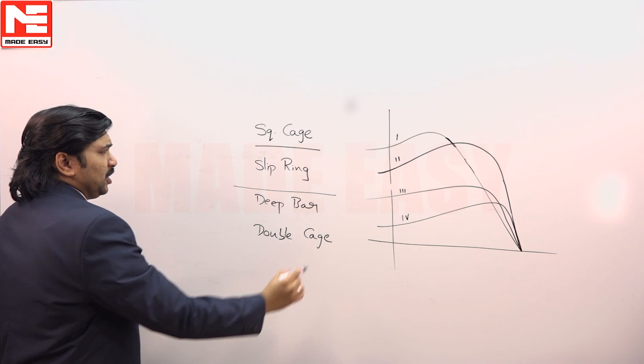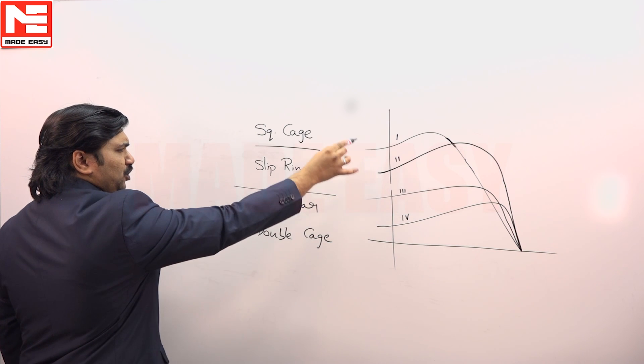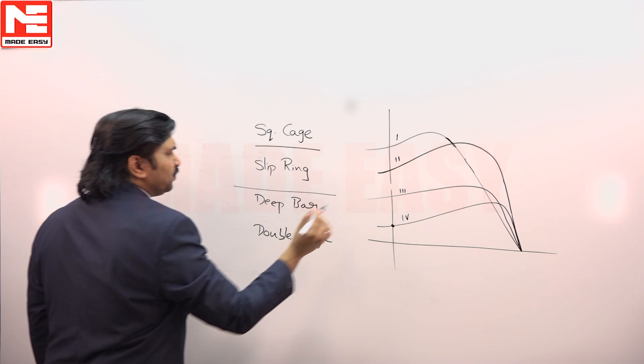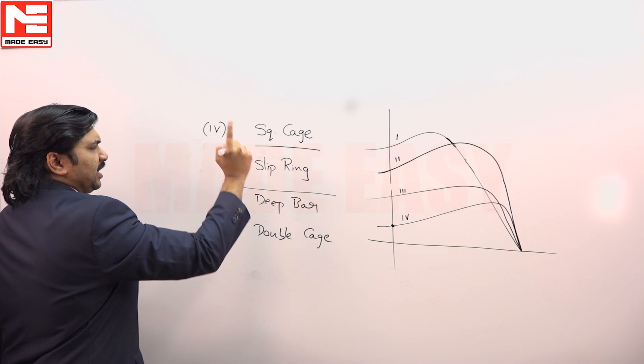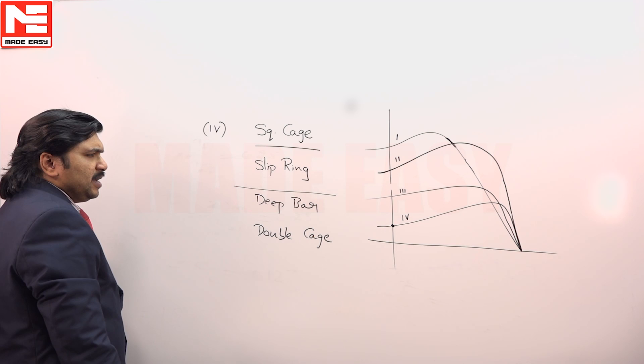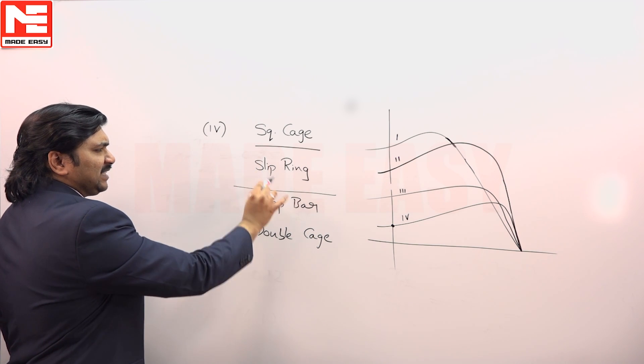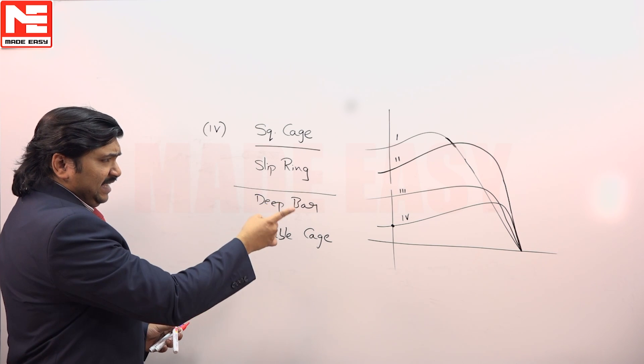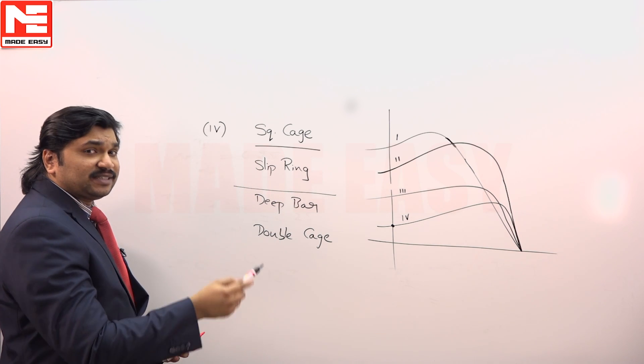So in all these four, which motors have low starting torque? This is the starting torque. So squirrel cage go to fourth one. By adding external resistance in series with the rotor, we make high starting torque come into picture. That is a slip ring.